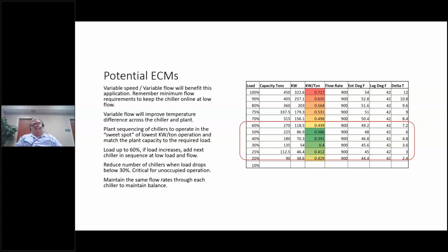Reduce the number of chillers when the load drops below 30%, critical for unoccupied operation. We had all those hours of unoccupied that it was working at a very low efficiency point. But if I don't have to run 2 chillers, go to 1. Make it pick up the load. Maybe you can get it up to 50%, the most efficient point, rather than running 2 chillers at 25%.